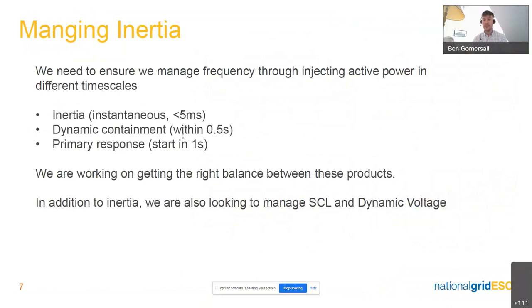In terms of what's driving that half a hertz per second value, it's the interaction, as we've said before, between the inertia, then dynamic containment, and then primary frequency response. What we're really interested in is keeping frequency stable through the injection of active power, and our inertia is injecting that very fast, either instantaneously or within the order of 5 milliseconds if it's grid forming. We then have something slightly slower through our dynamic containment products, and then something slower again through the traditional primary frequency response. There's work ongoing trying to get the exact balance between those, but if we can use inertia to keep rate of change of frequency down to about half a hertz per second, that seems to be the right balance. And you get very complicated interactions, with 4 and 5 dimensional graphs of various different components all interacting with each other.